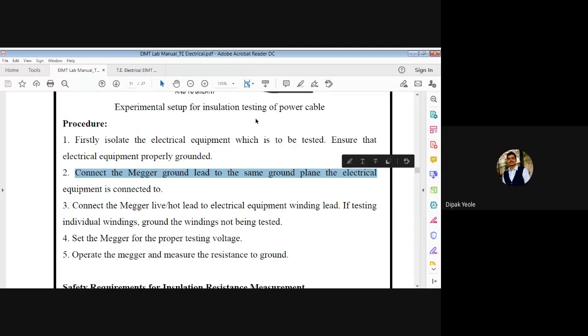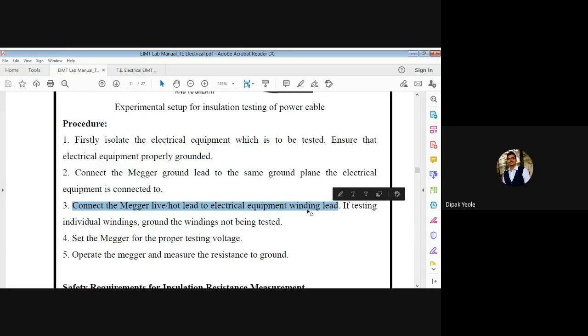The procedure we connected above is written here. Next, connect the megger live or hot lead to the electrical equipment winding lead, wherever the winding lead is, that's where we connect the live terminal. If testing individual windings, ground the windings not being tested — this is the precaution they have taken.